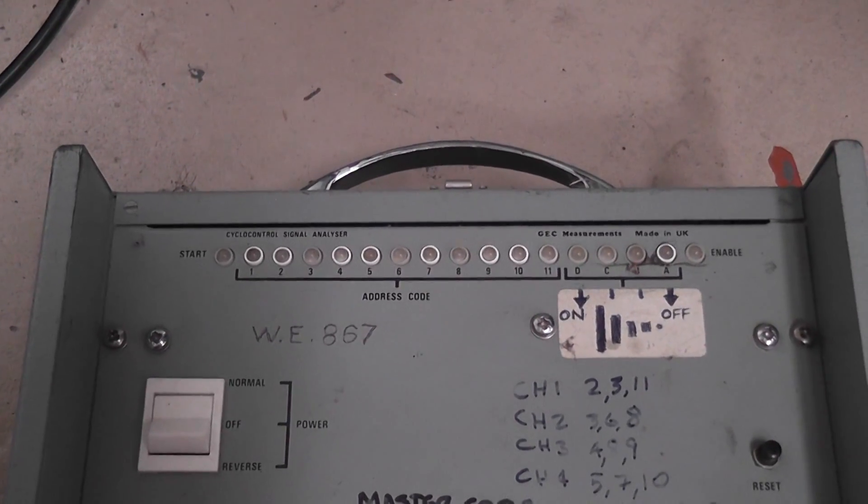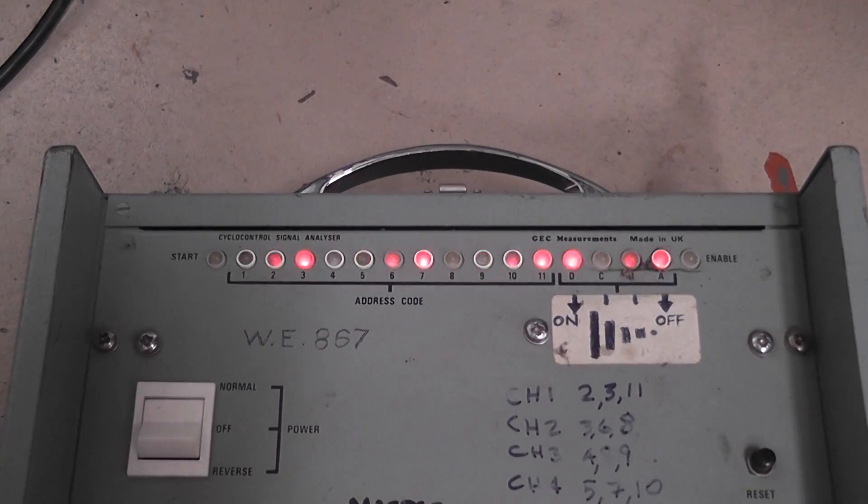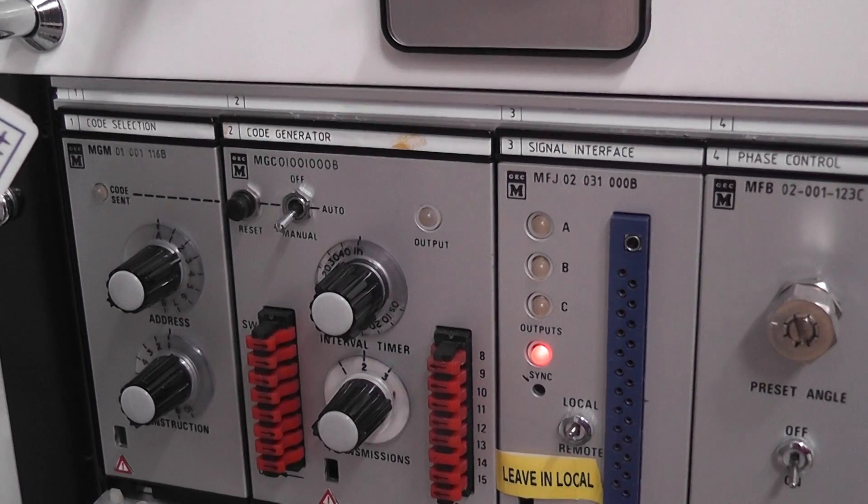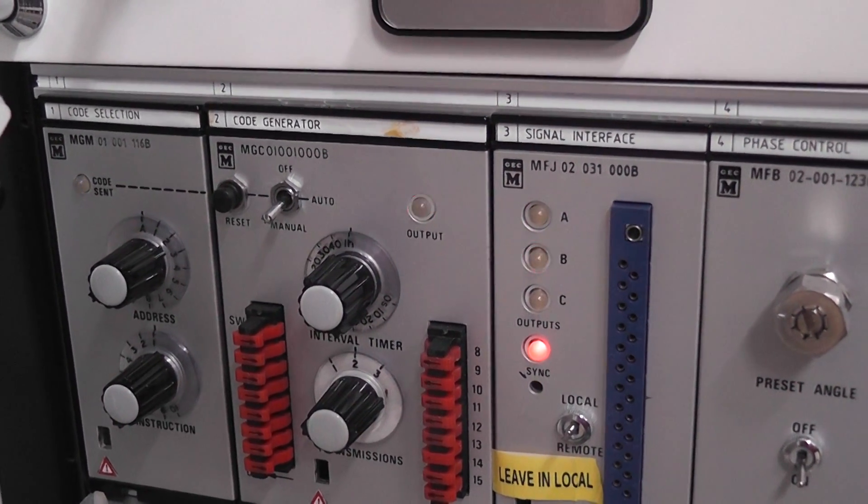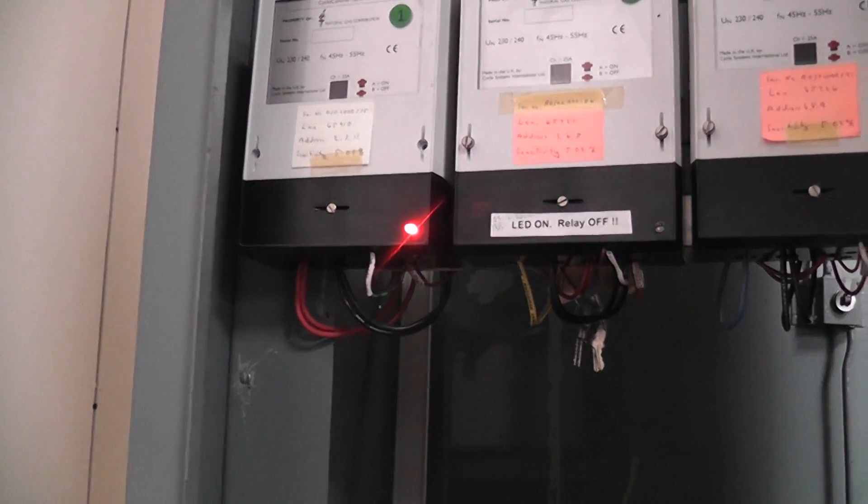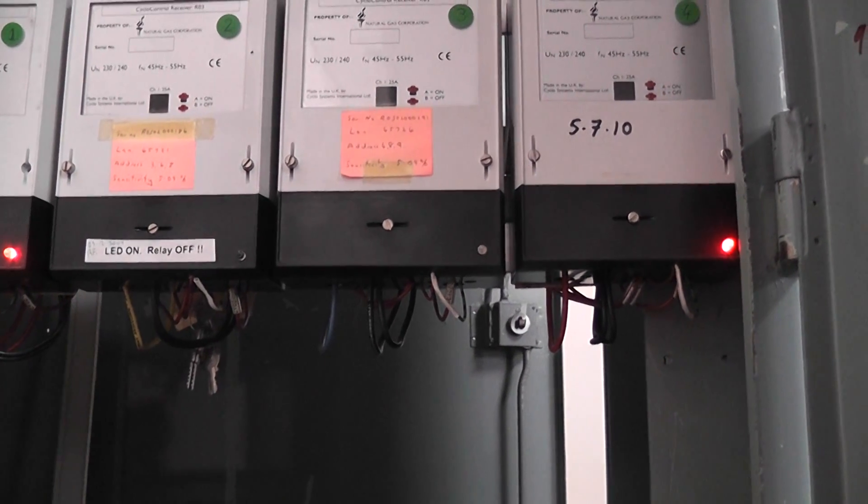Let me check this. Channel 3 code. Channel 3 code. These two relays are on the red phase, so I think the red phase is dead. I need to check that out.